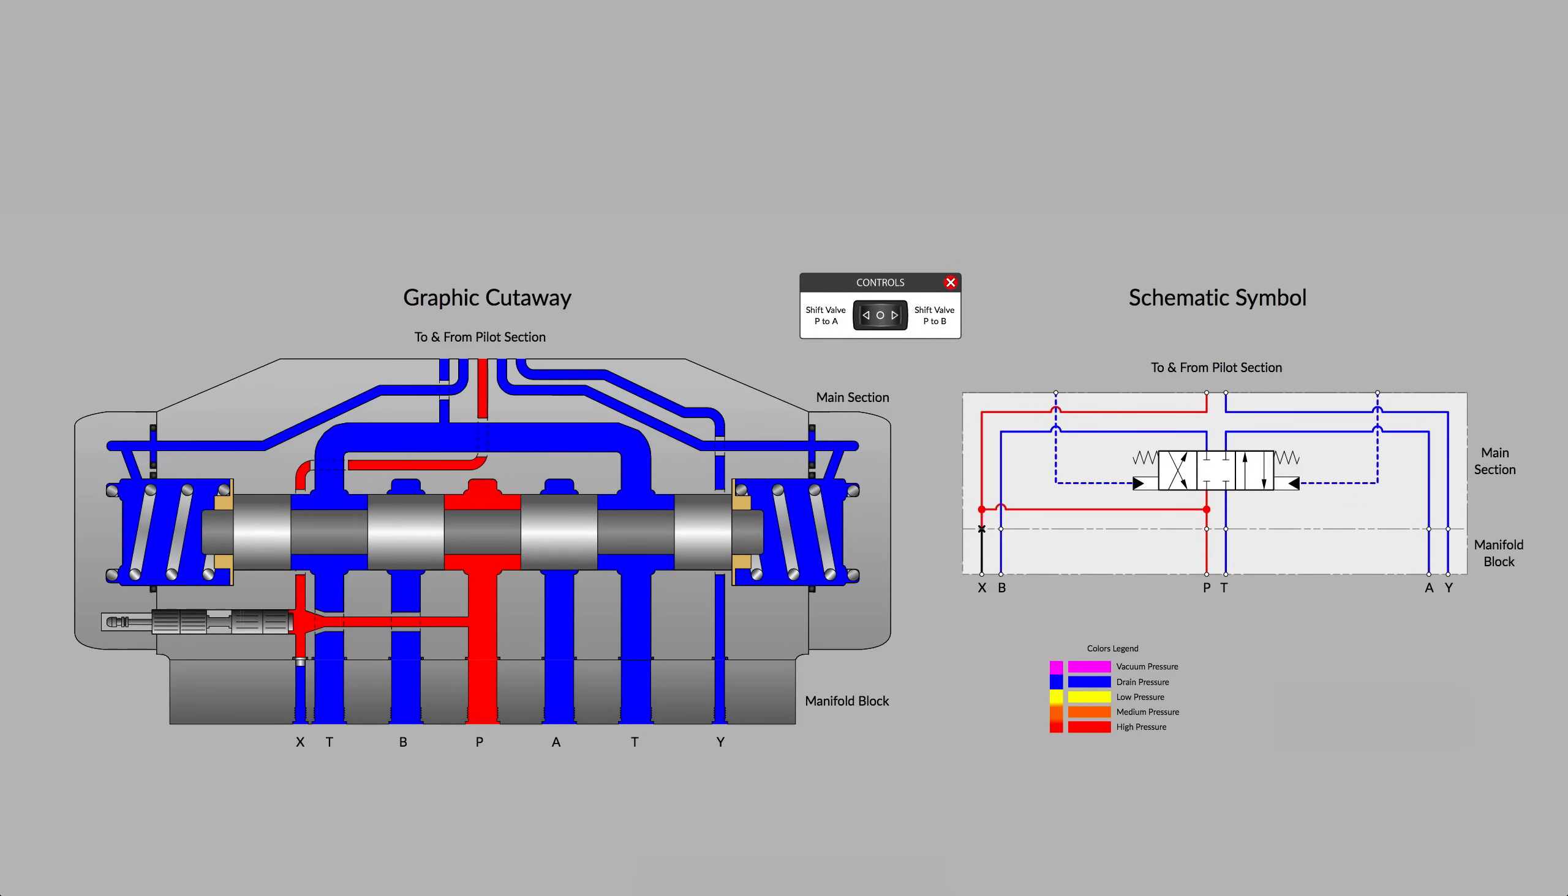The main section is nothing more than a very large spool-type directional control valve. The spool in these types of valves could easily be one inch in diameter or larger, 25 millimeters or more. The length could easily be a foot long, 30 centimeters. And flow rates could easily be 100 gallons per minute or 400 or 500 liters per minute or more. So these are very large valves.